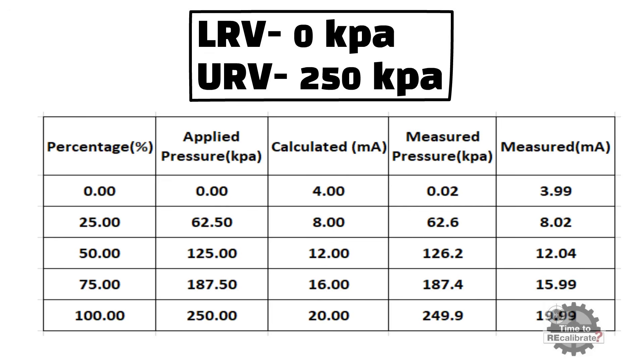Now apply 62.50 kPa pressure to the transmitter by using the pressure calibrator, and the transmitter display will show you the measured pressure value. The measured value should be near to 62 kPa. A plus or minus 5 kPa deviation from the standard value should be acceptable. Also note down the measured milliampere value which is measured by the digital voltmeter. The measured milliampere value should be near to 8 milliampere.